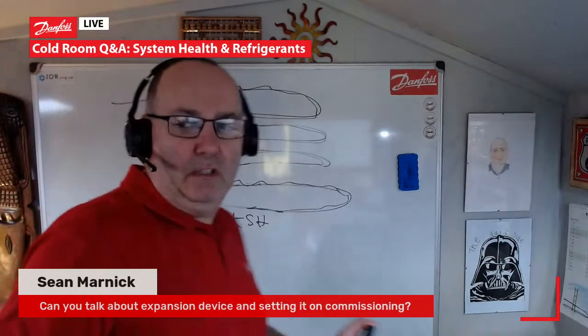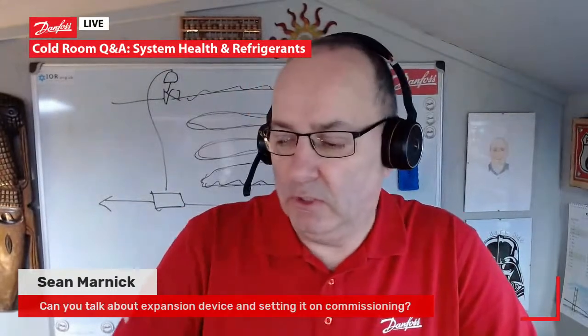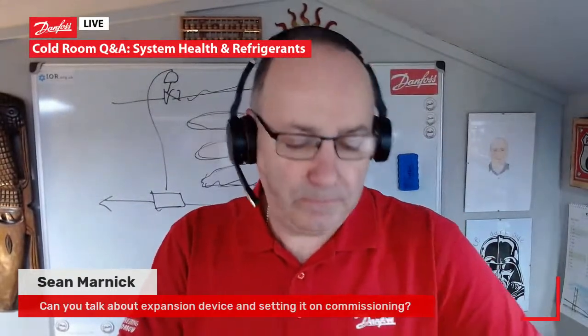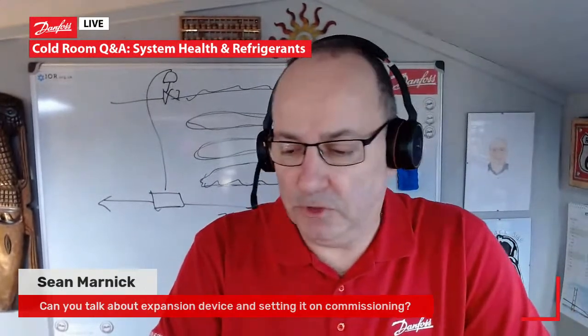So when you're commissioning, Sean, most important, check your superheat on your evaporator, but then also check the suction superheat coming back to the machine as well, because we don't want to cook the machine either. So hopefully that answers that question.